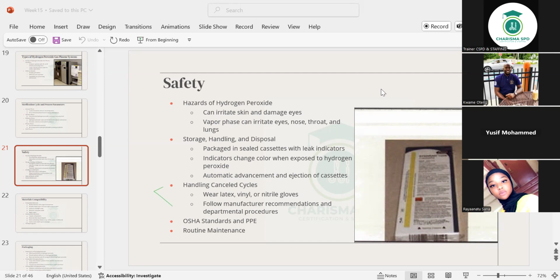So always be careful. Don't just take the cassette and place it in. Observe the marks on the cassette. That's what I've said: when you are there, be very critical of your surroundings, things on the walls, things inscribed on the papers and pouches you're using. Don't just take a pouch and say, oh, this is steam, so I'll use it for steam. No. Look at it. What is written on it? Is there a chemical indicator on it? Is it steam or low temperature? The same way with this cassette, look at it. That yellow light is there for a reason.